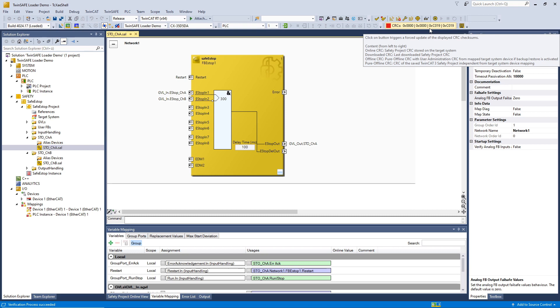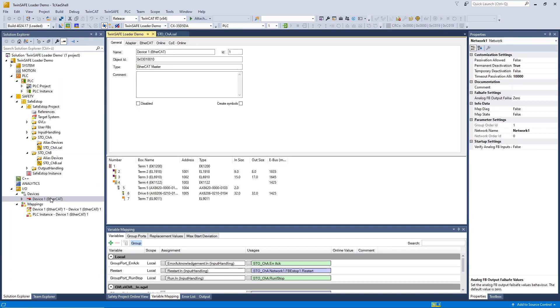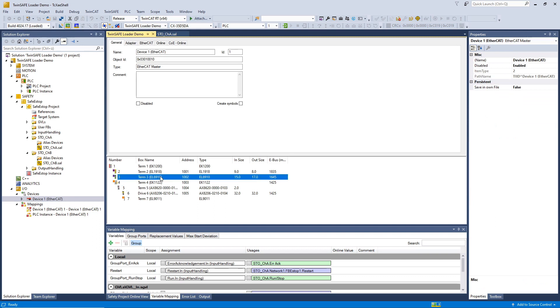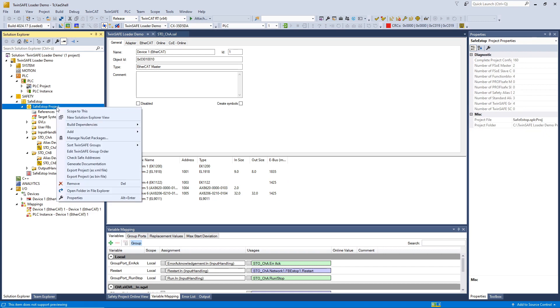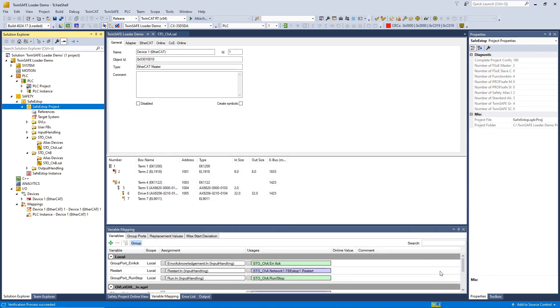After designing our safety project, we check if it's valid. We note the CRC, which in our case is C019 — we will need that CRC later for the activation of the safety project. We also need the EtherCAT address of our EL6910 target system. Going to the EtherCAT configuration, we see that the EL6910 has address 1002. In order to download the safety project with the TwinSAFE Loader, we need a binary file, so we choose 'Export project as bin file' from the context menu and save it to our hard drive.